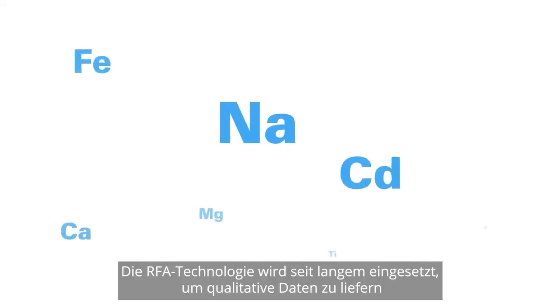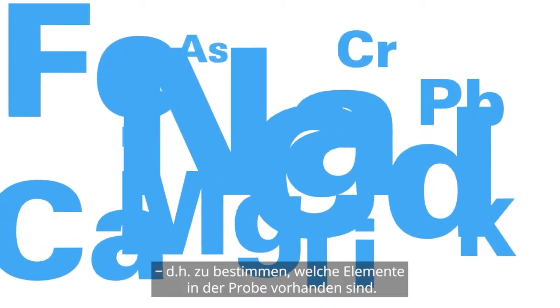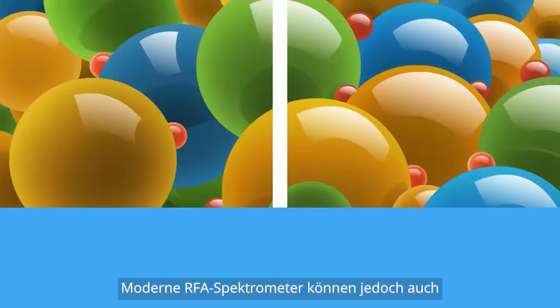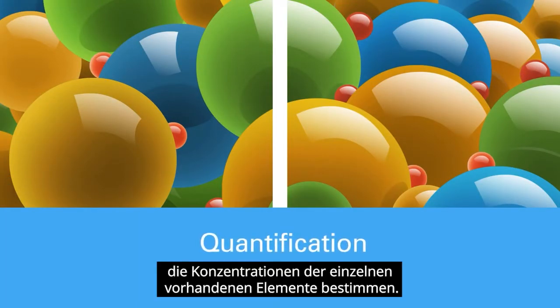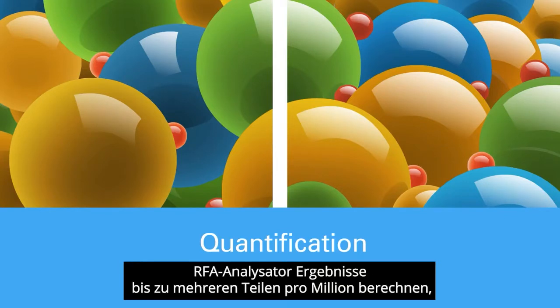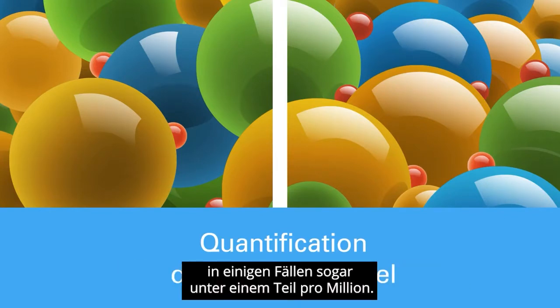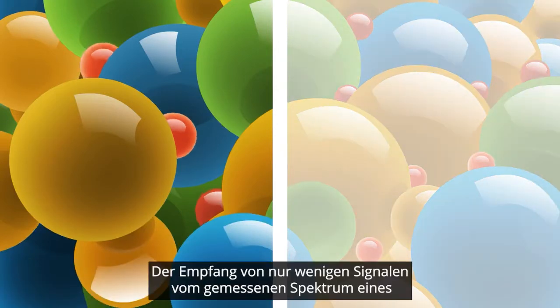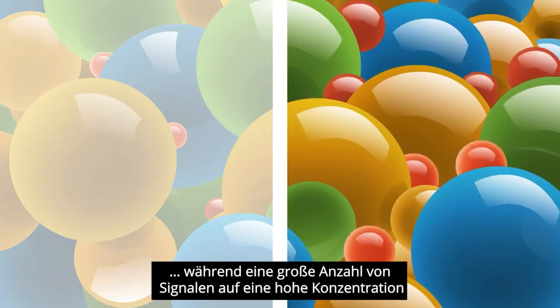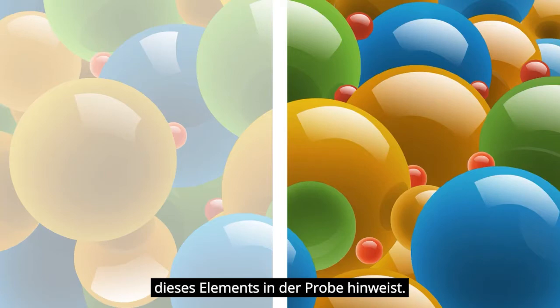XRF technology has long been applied to deliver qualitative data — determining what elements are present in the sample. Modern XRF spectrometers can also determine the concentrations of each element present. When you want quantification, an advanced XRF analyzer can calculate results down to several parts per million, in some cases even below one part per million. Receiving only a few signals from the measured spectrum of a specific element indicates a low concentration, while counting many signals indicates a high concentration of that element in the sample.